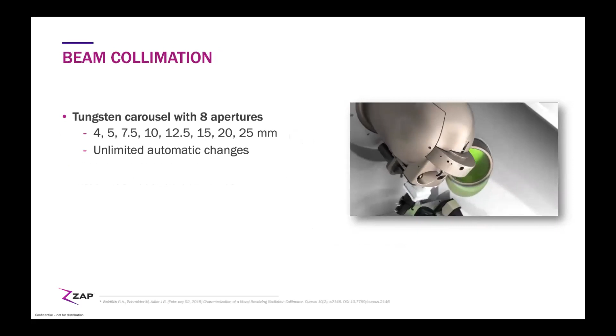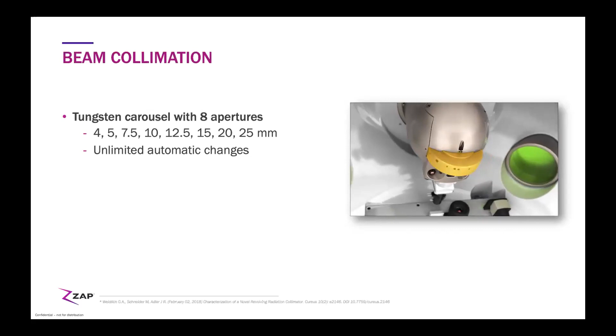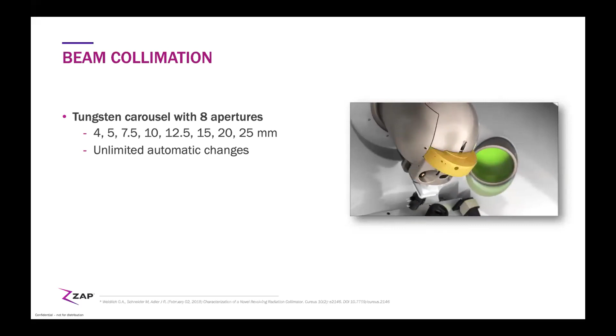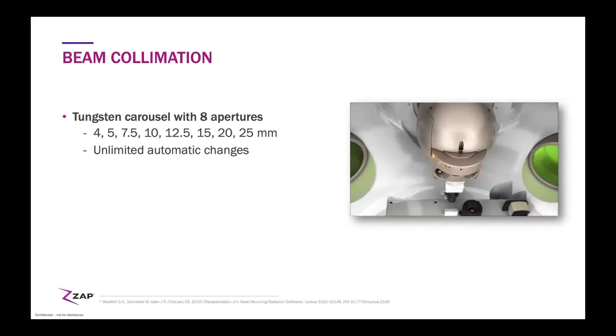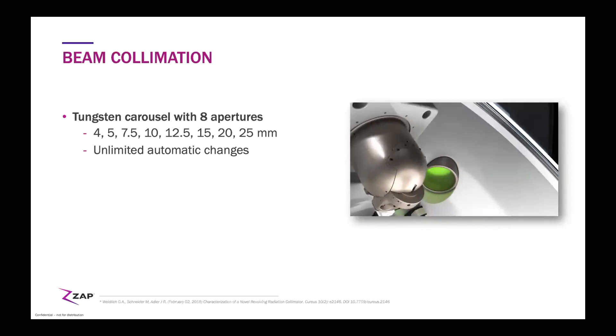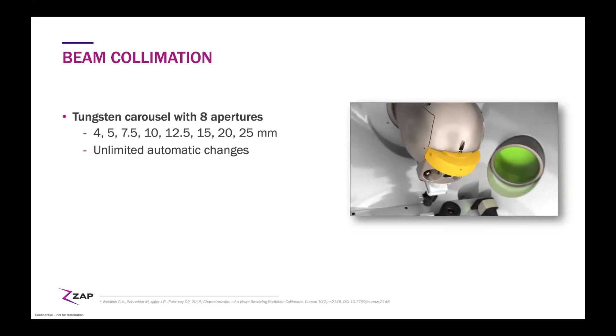So now the collimation system is really cool. Here you have an example of our spinning disc, which has 8 different apertures drilled through this tungsten wheel. Literally in a second or two, we can change aperture sizes from 4 millimeters to 25 millimeters in various different increments. And this gives you throughout the procedure just infinite opportunity to change this beam size, the beam dimension. And this too is part of the secret sauce that gives us the brilliant dosimetry that I've been alluding to.